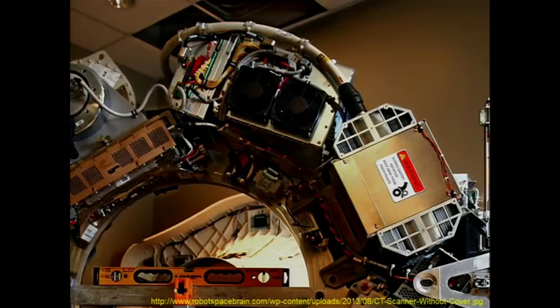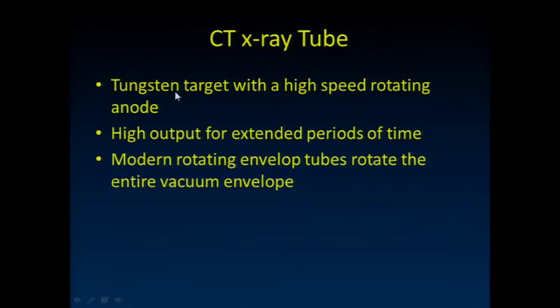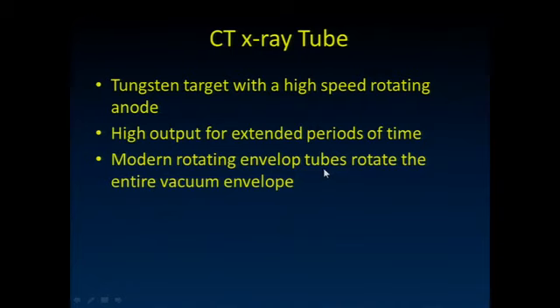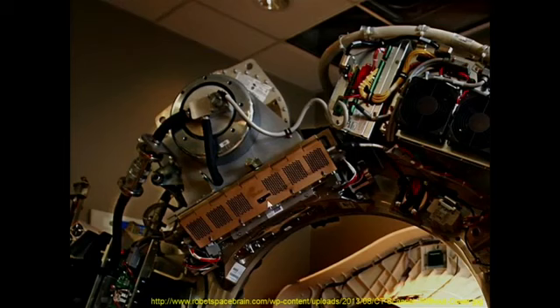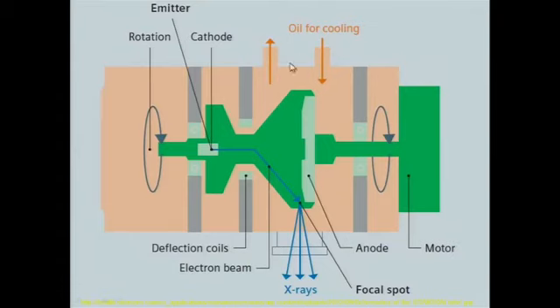Here's the power supply with big cables coming in. We need an x-ray tube that can absorb a tremendous amount of heat and still function well for multi-phase studies covering chest, abdomen, and pelvis. The engineers have done a wonderful job—I remember from my first day as a resident actually having to wait a few minutes while the tube cooled down. With modern tubes, you could put a conveyor belt going into the CT scanner. Here's the x-ray tube with the window where x-rays come out. We have a rotating cathode in an evacuated tube—we actually rotate the vacuum. The seal is so good we can pump in cooling oil to prevent heat damage.